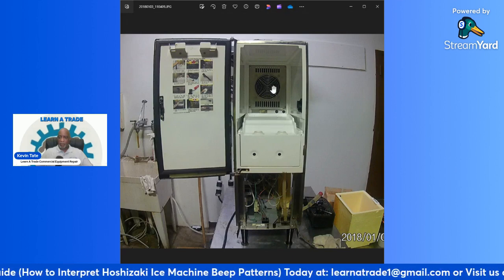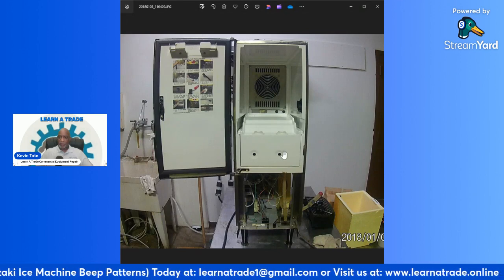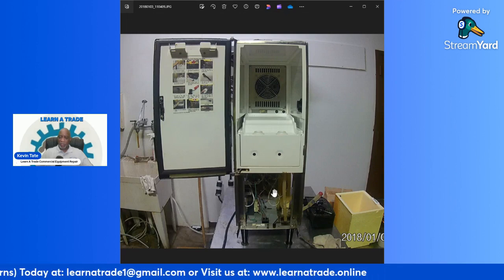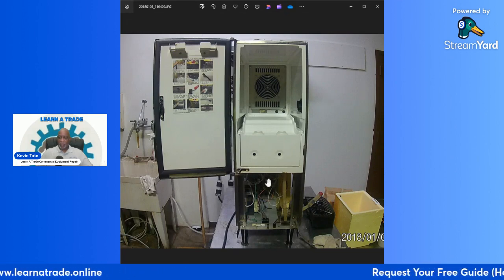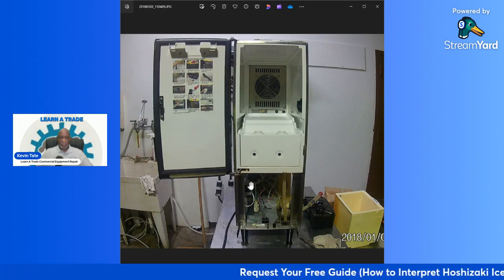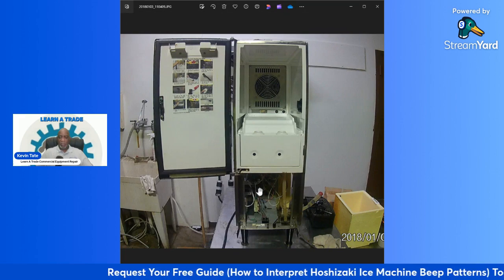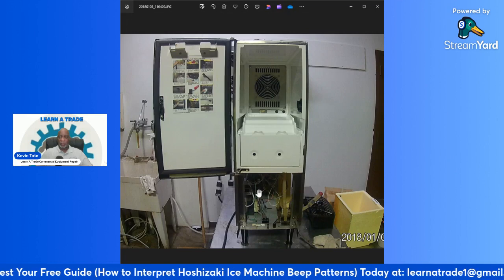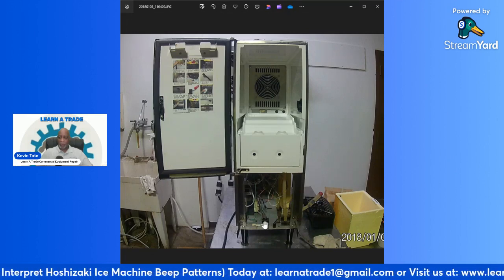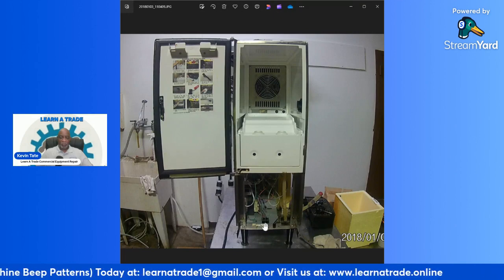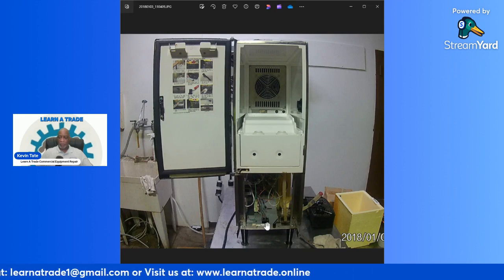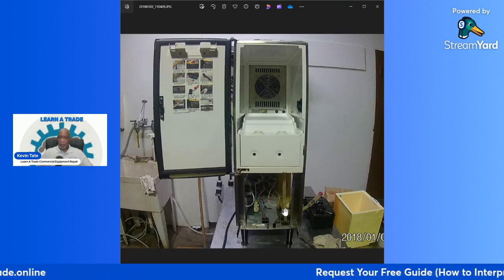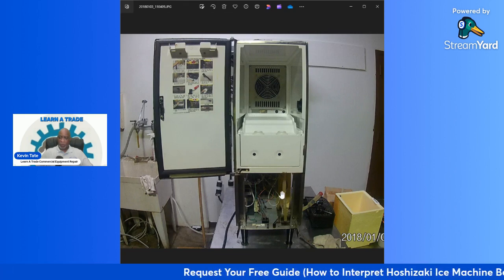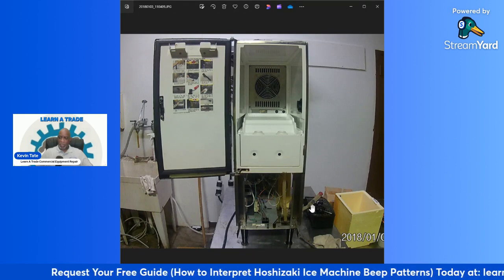So this is the evaporator fan area, and this is the cabinet area. Down below is the control board. Right in here you have the control board, the transformer, the relay, the start relay, and the control switches for the compressor and the pump to operate. Then down here there's a dispense switch you can turn on or off, a drain tube right over here, and the fill tube sticking out the side.